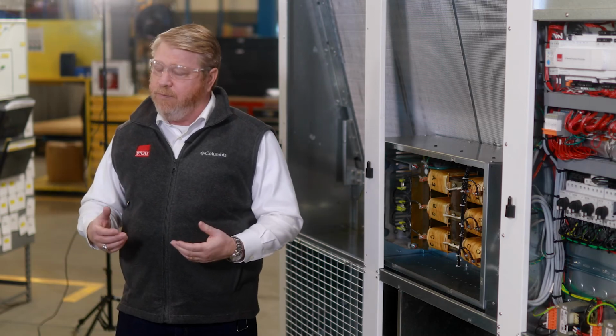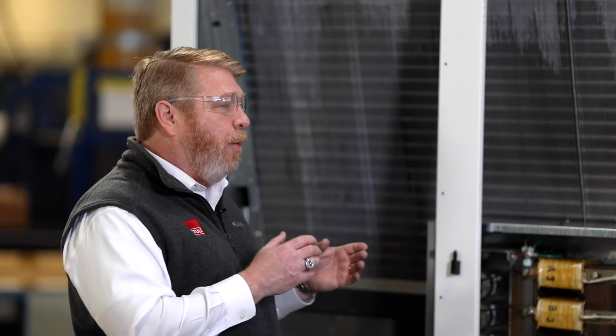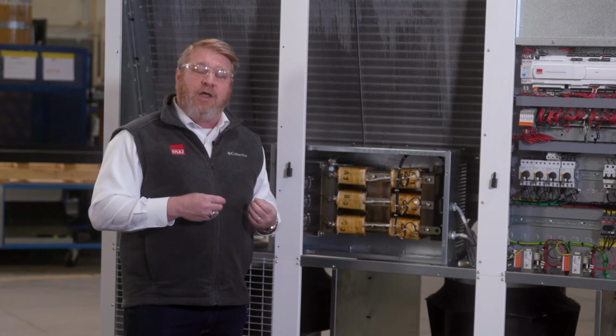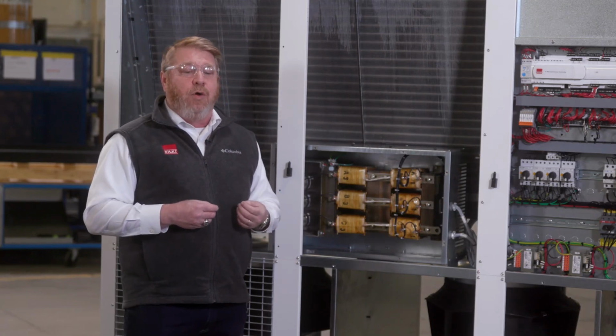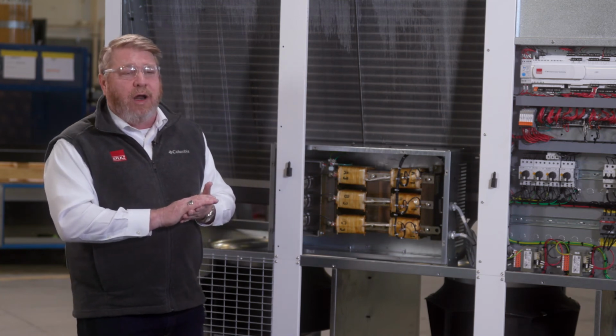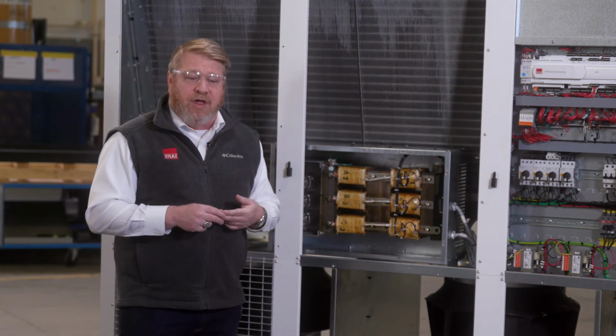Now, the way we approach this is we use either an active or a passive harmonic filter. What this does is it filters out the signal such that we get much closer to the original sine wave signal that was coming into the unit. By filtering these harmonics, we're able to lower our peak current, maintain temperatures within the device, lower the electromagnetic emissions of the unit, and also protect the core of the motor.